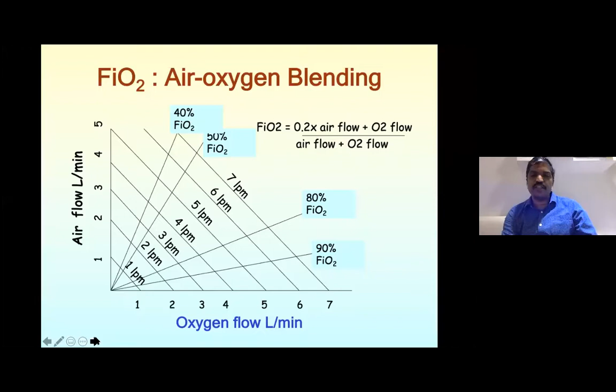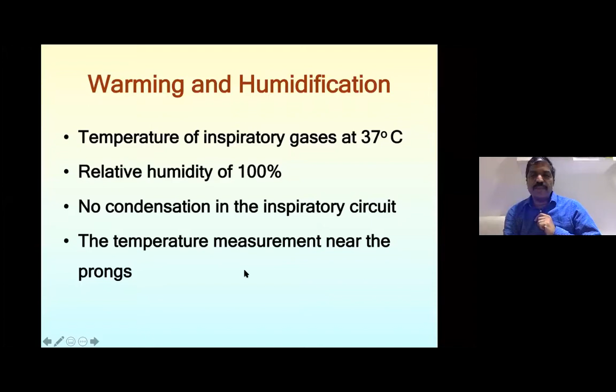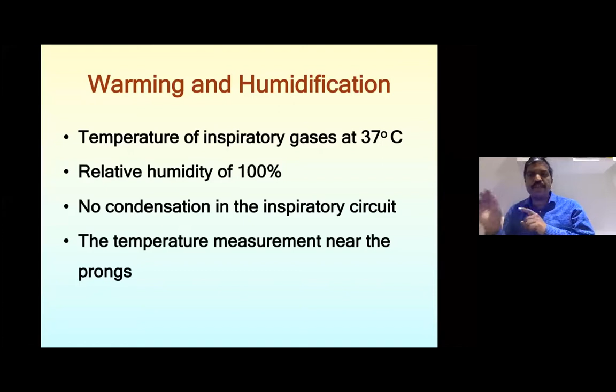We have already said that humidification is very important. There are no ranges. Your humidifier should give 100% relative humidity. To ensure that you are giving correct humidity, there should be no condensation in your blue tube. Where there is heater wire, there should not be any condensation. In the expiratory limb, there should be small mist. Then you know you are giving humidification correctly. Your humidifier should show 37, no condensation in inspiratory limb, some mist in the expiratory limb means you are giving the correct humidification for the baby.